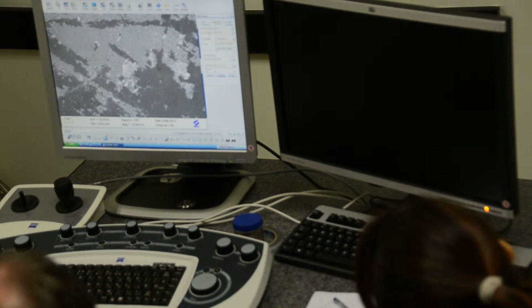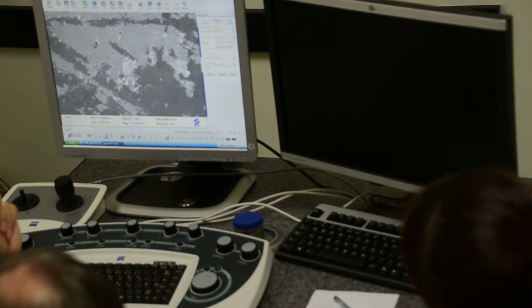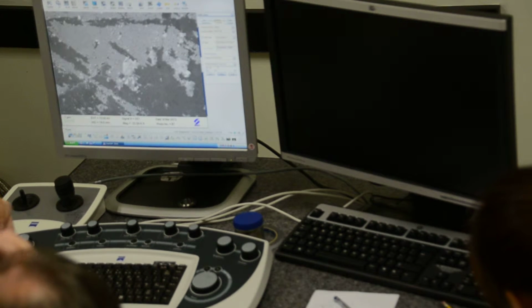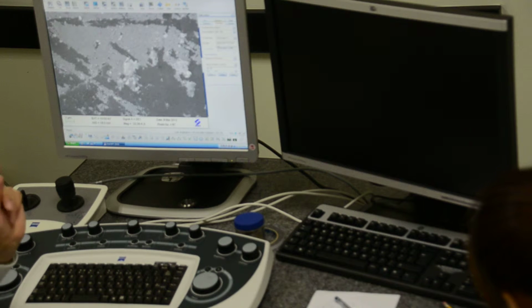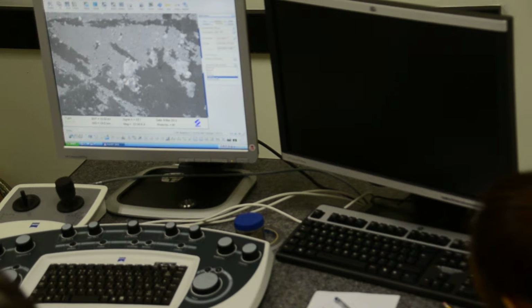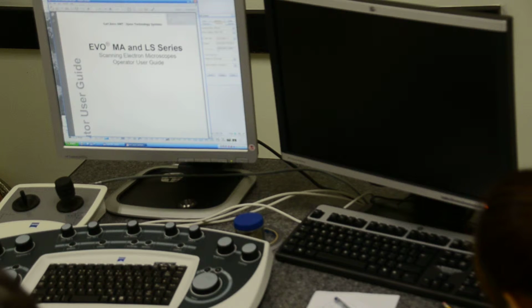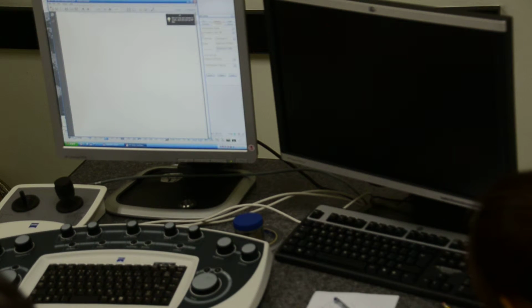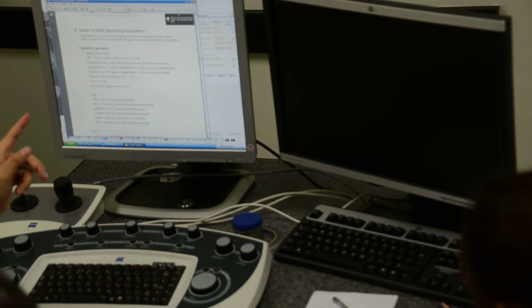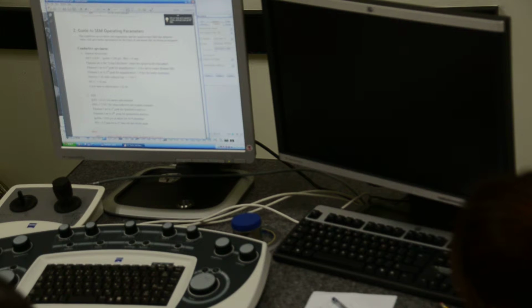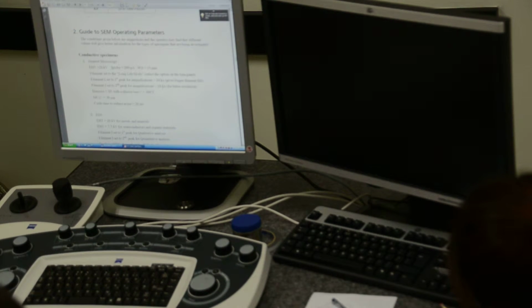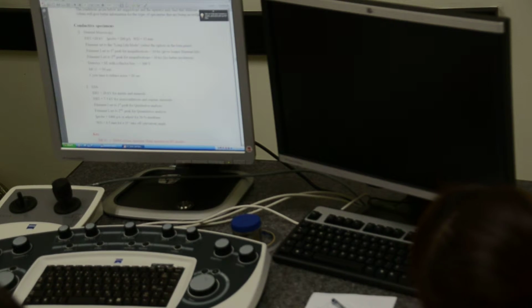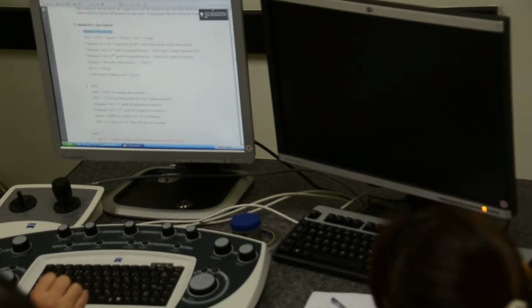So normally for good image quality, I would prefer the line average, n equal to 60, or scan speed about 3. But it's also very subjective to your image quality itself. Because if we go to the help, it says the user manual. You should read out the menu itself. But generally, I'm going to look at this called Guide to SEM Operation Parameter. So for conducting samples, the general imaging condition for normal daily work, the routine job.